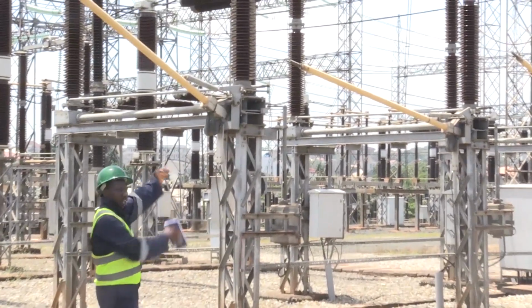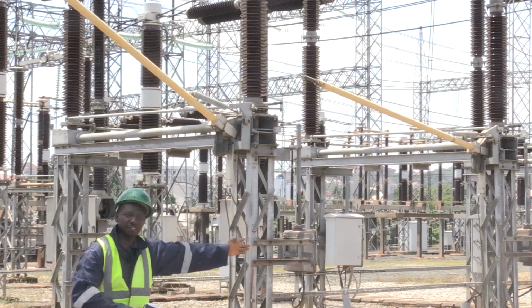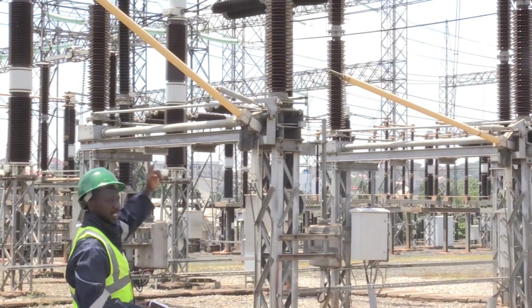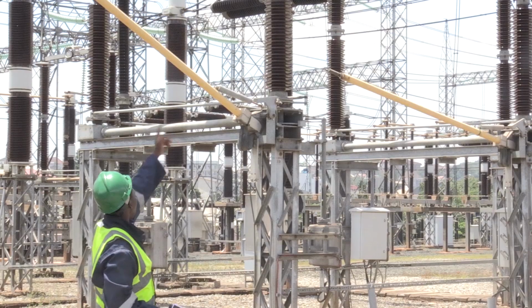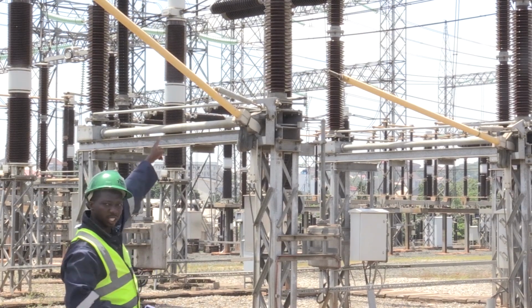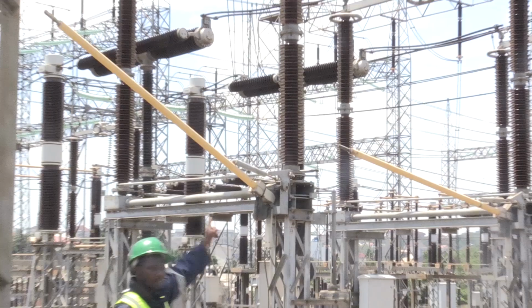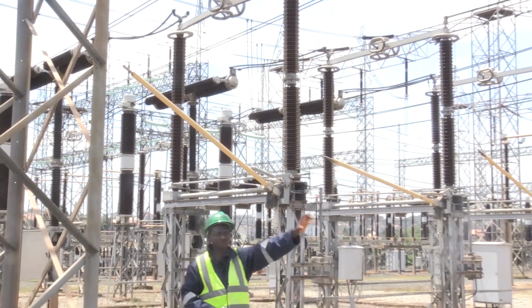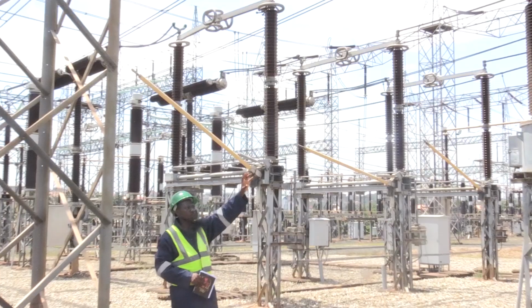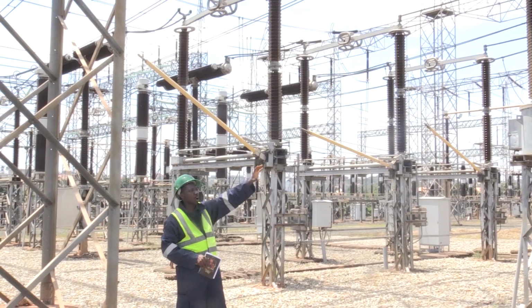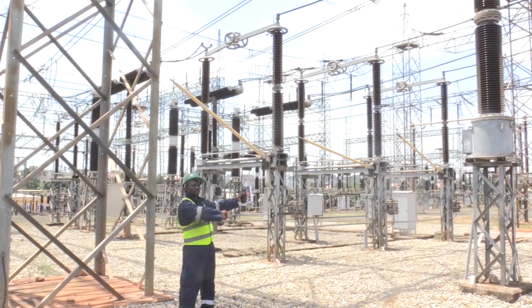This grounding stick here, you can see the yellow sticks, 3 of them for the 3 phases. We activate it by grounding the line. This stick goes up and hooks by the isolator base, thereby discharging whatever residual charge we would have on this transformer. We also have to isolate the other end of the secondary so that we don't have a backfeed, and then at this point we are now safe to work.